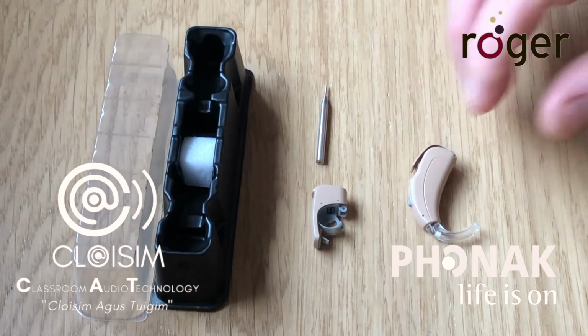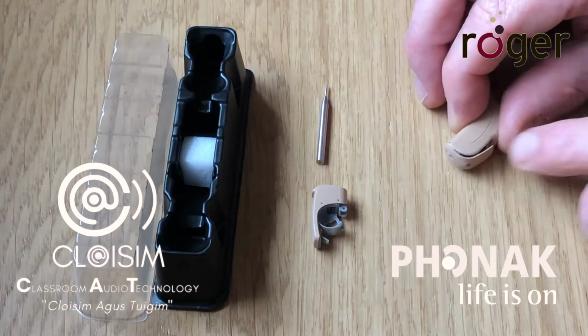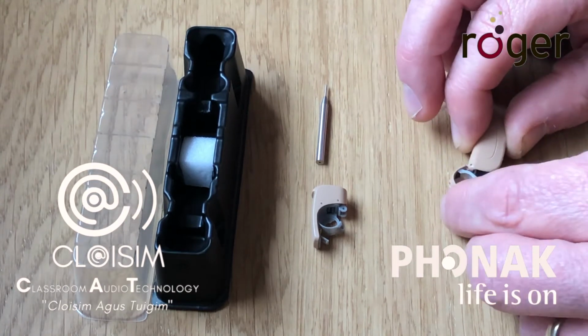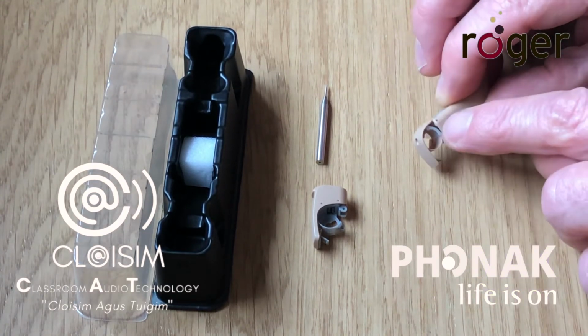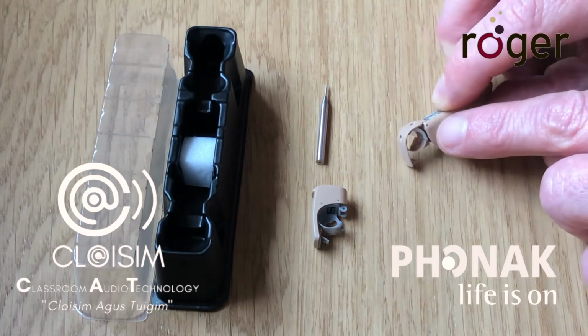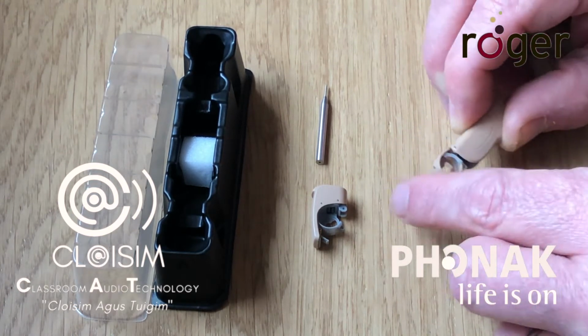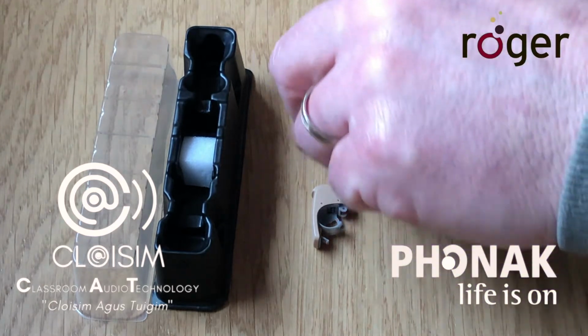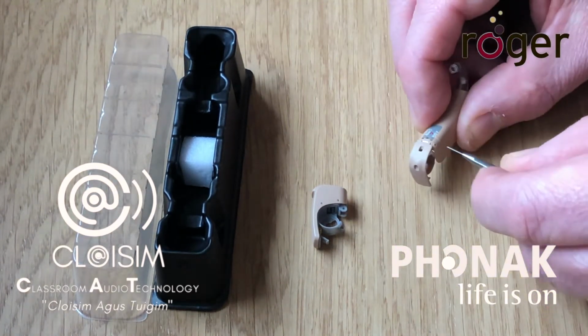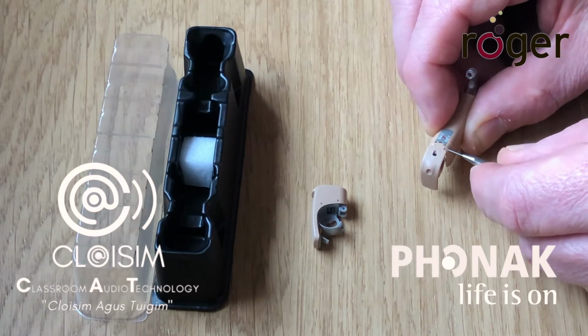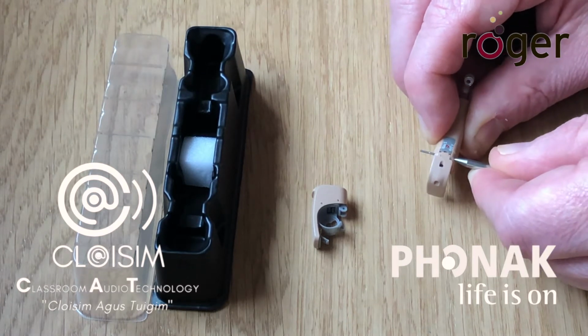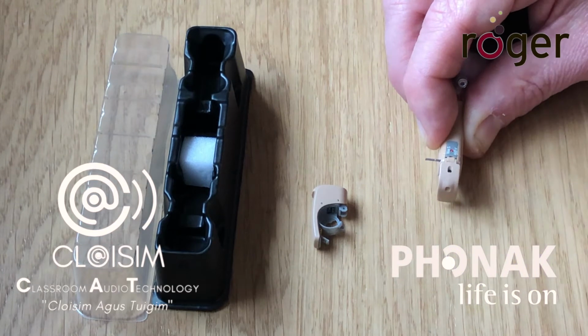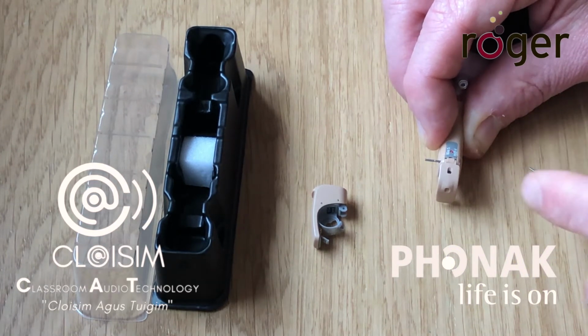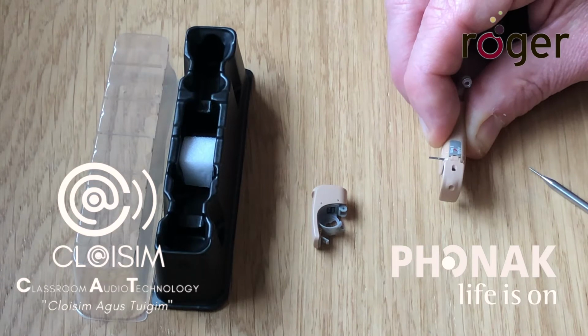hearing aid. So we take the hearing aid like so, and this is the battery tray. The existing standard battery tray opens and closes on a fulcrum, a little bar that runs from one side of the hearing aid to the other. We're going to remove that bar with the battery tray removal tool, pushing from one side to the other. You will push the bar out that side. It doesn't fall out, it's designed just to hold there. It doesn't always stay there, so do this on a clear table or with some tissue paper underneath. You don't want to lose that bar.